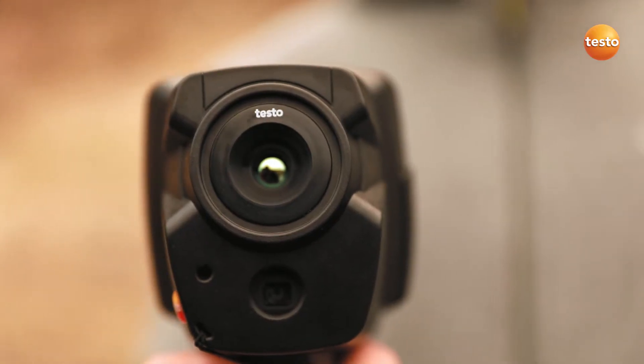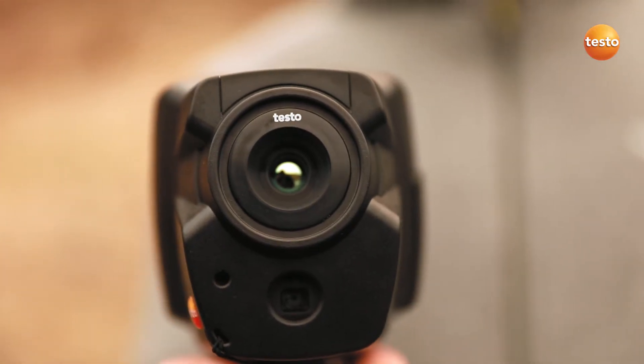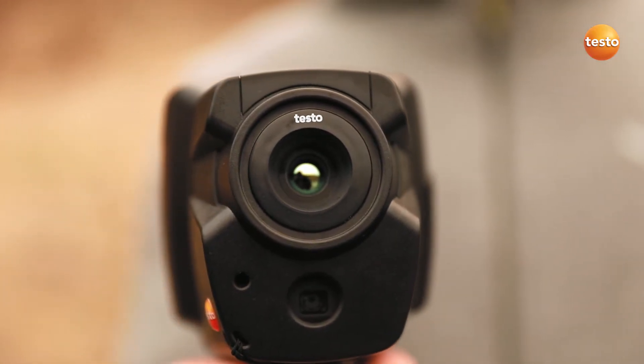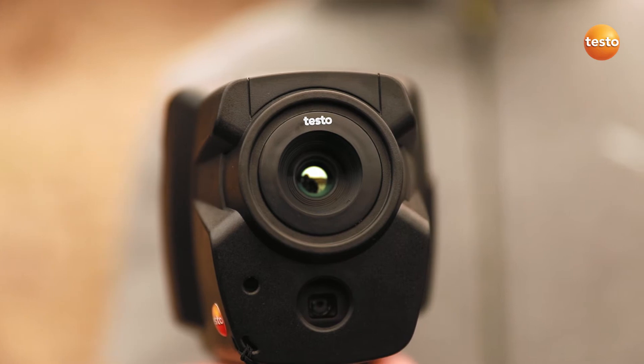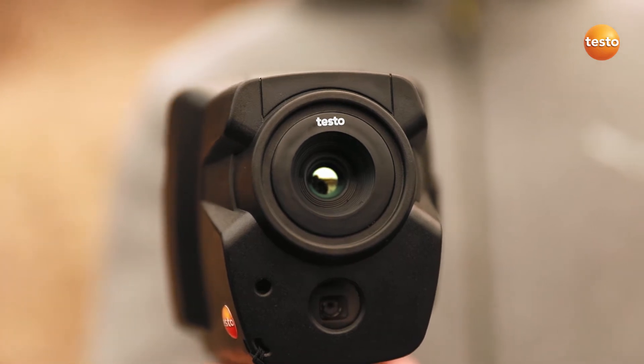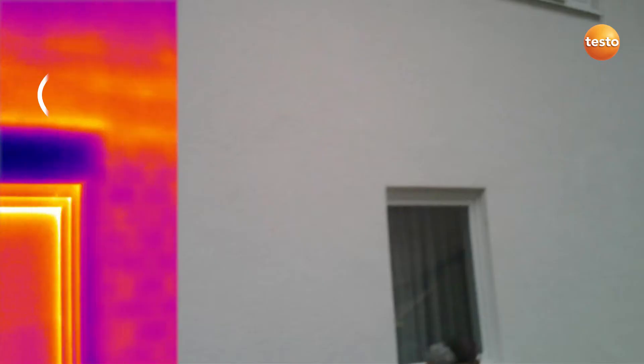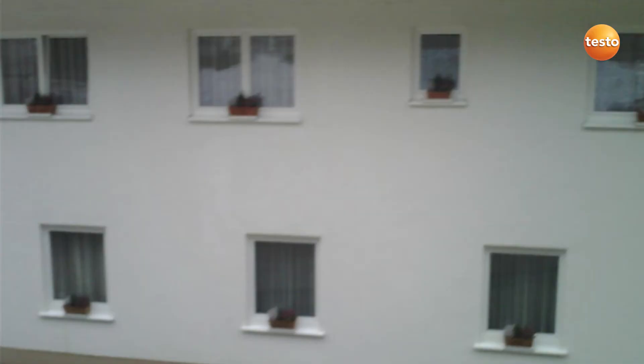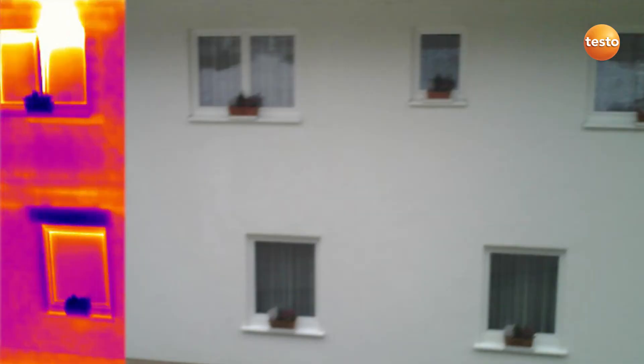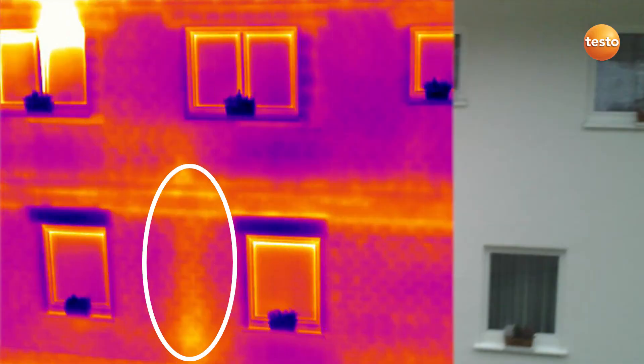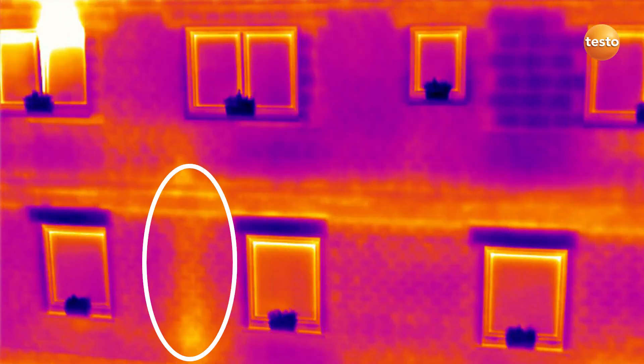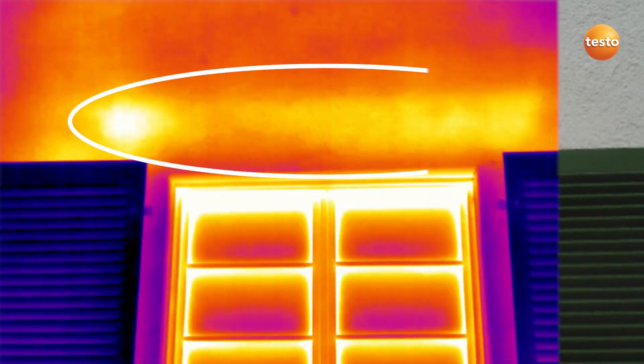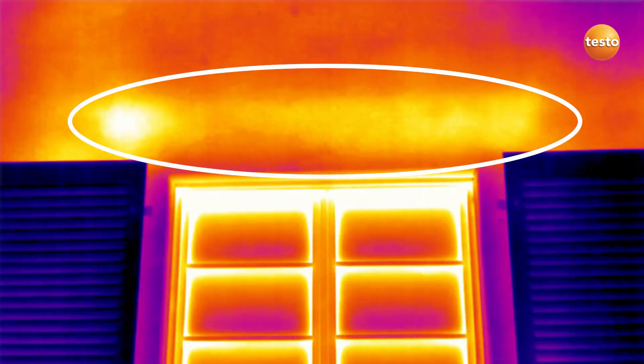Let's see which faults we can identify with the Testo 872 on the facade of this building: a cold bridge along the hole of the intermediate floor, the badly insulated riser of a radiator, and an unmistakable air leak at a window lintel.